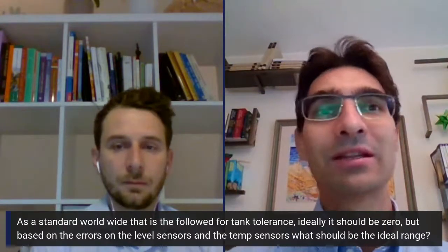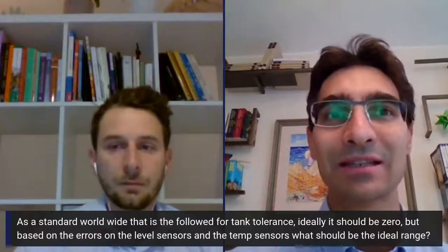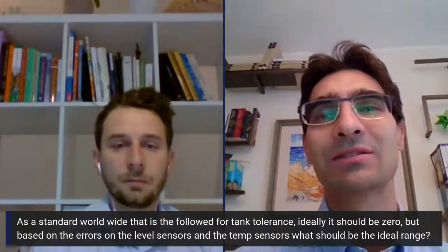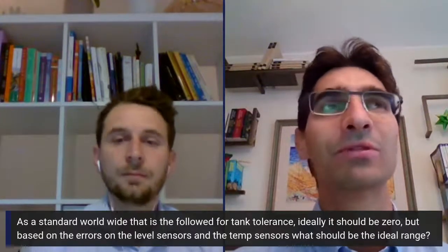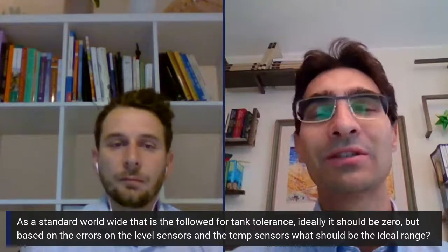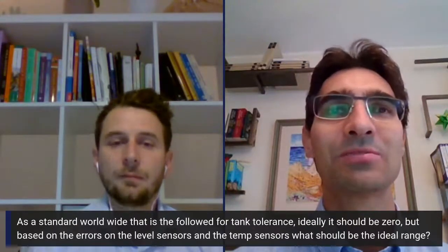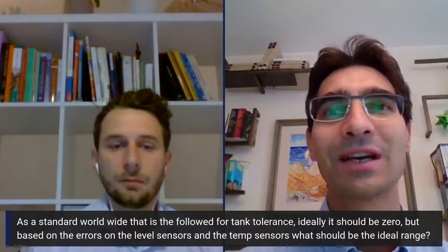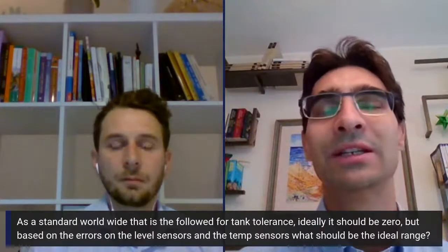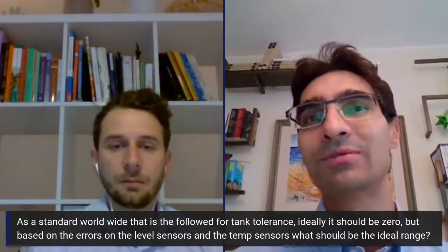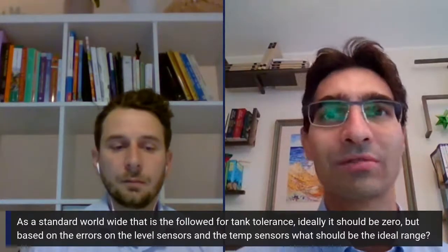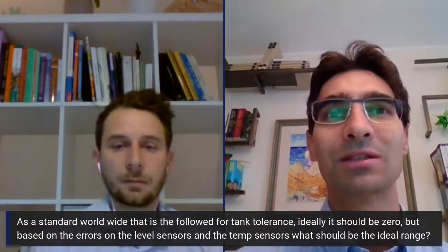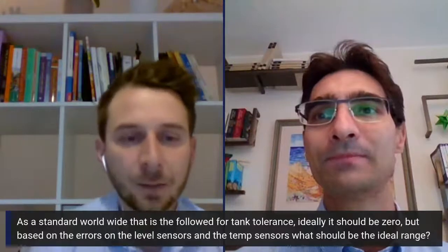The other big variability is the density. So not only the level and the temperature, but in some cases, the crude is one case, and we touched it before. The other big uncertainty, for example, is in the slops. Slops, typically we have very, very poor information. You have hydrocarbons, water mixed all together. So there it's quite difficult. In that case, for sure, the uncertainty that should be associated with these tanks is much higher. So there are several factors to be taken into account. Okay, thank you, Marco.